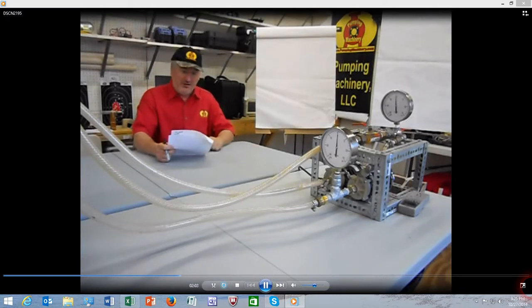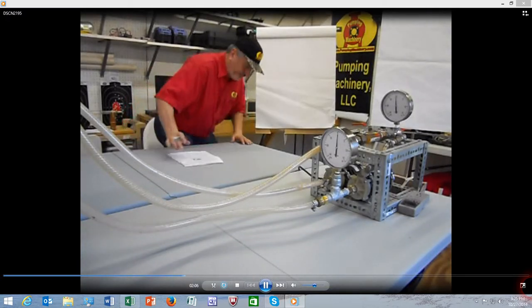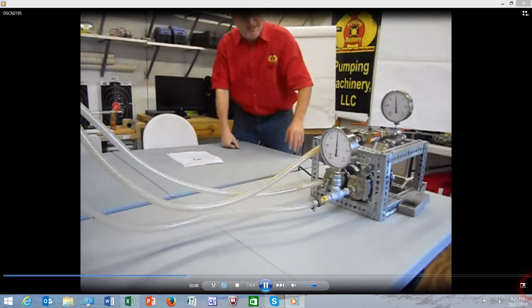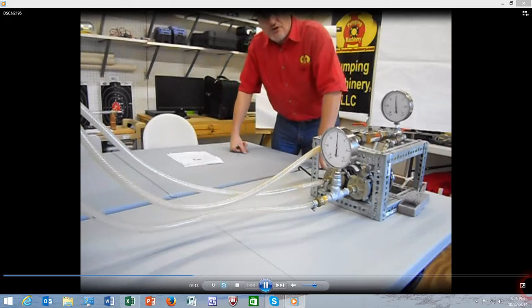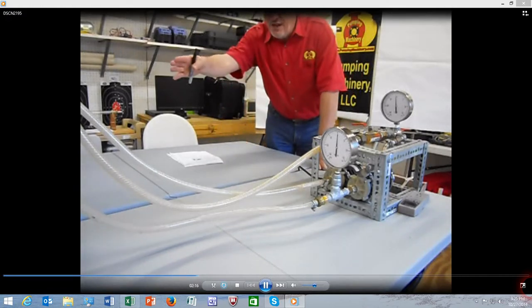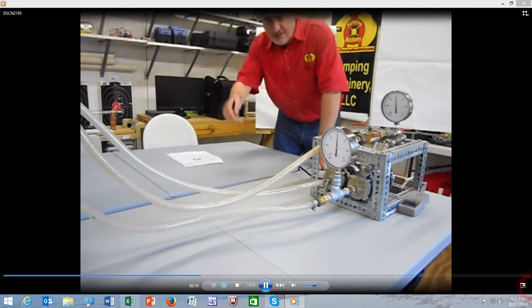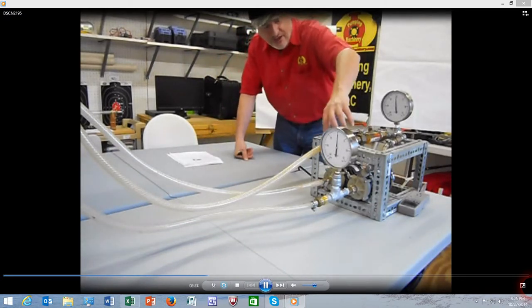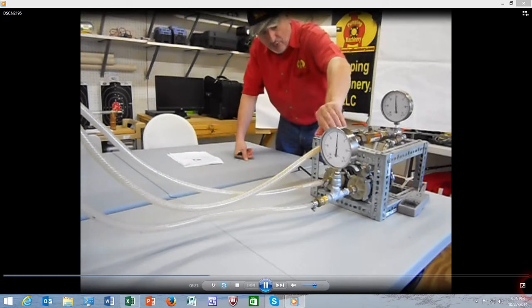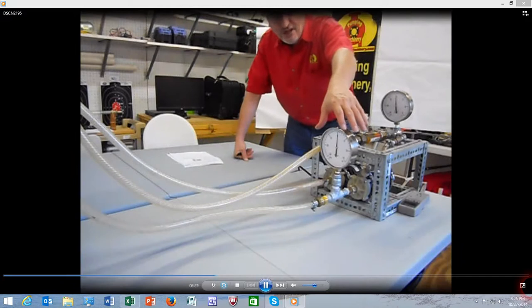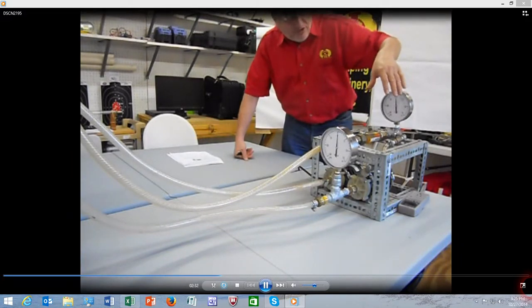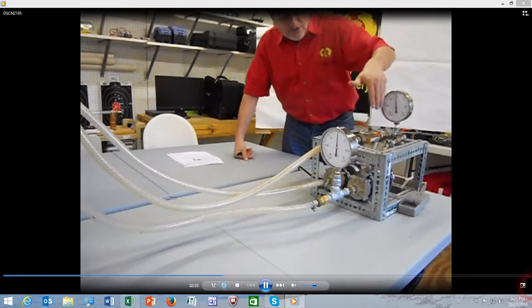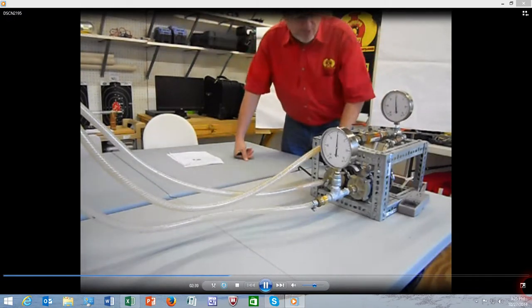So we'll do our testing today. We'll start with running the pump. We have the unit, we have our testing module. It has two centrifugal pumps, small centrifugal test pumps. They take suction from the tank and return the flow back to the same tank for simplicity. There's a discharge side with a valve right behind the gauge here. I can open the valve or close it. Suction pressure is measured by this gauge, and the discharge pressure is measured by this gauge. There's a flow meter on the discharge side, through which the flow is returned back to the tank.